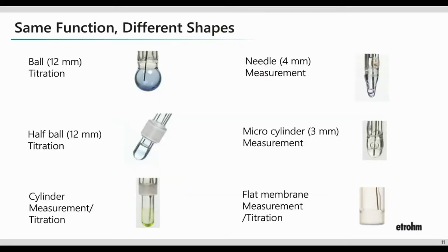So electrode, membrane, or bulb, we've got that now, how it's working. Now, after this session, you may go and look in that infamous electrode drawer and notice that not all of the bulbs look alike. That's actually on purpose. The membrane can be made of different types of specialty glass to help improve performance in certain types of samples. So just like you would use a different sample container for a non-aqueous sample versus, say, something just like water, different glass material is more optimal depending on the sample type.